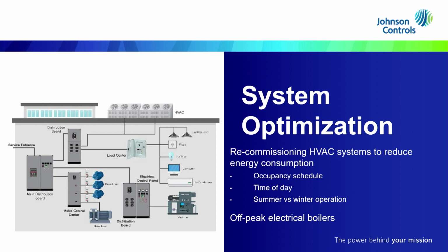By introducing off-peak electric boilers, we can ensure that the peak demand for the site does not increase. It also reduces the chances of having to do a service upgrade, which can be very expensive, and at the same time puts them on the roadmap towards decarbonization.